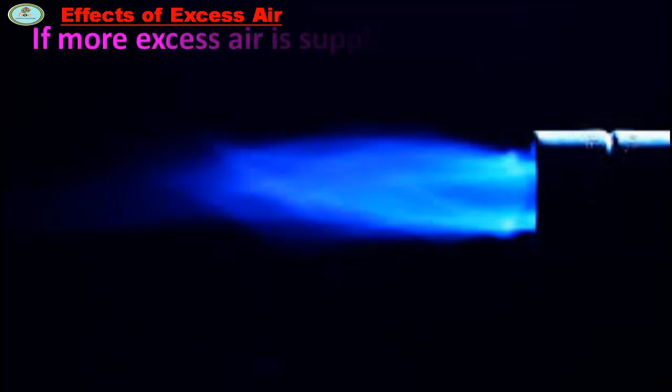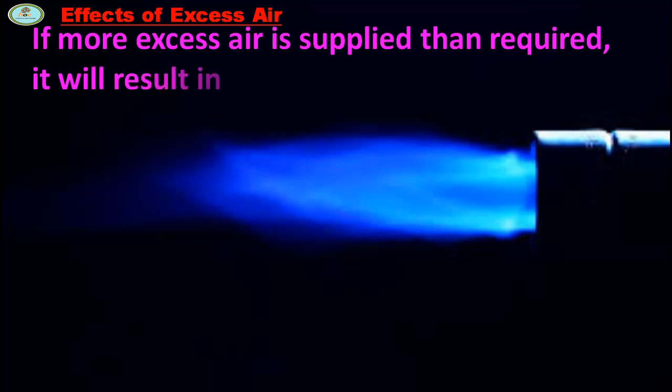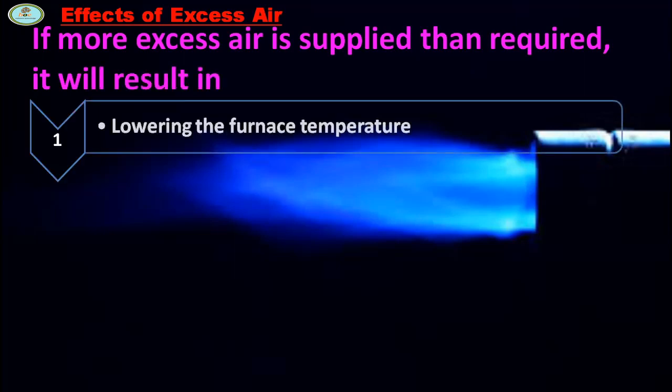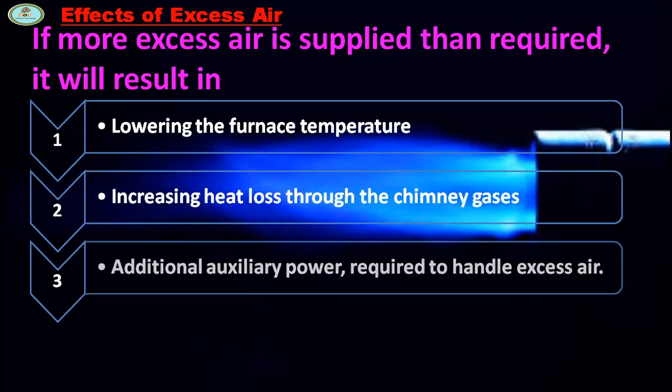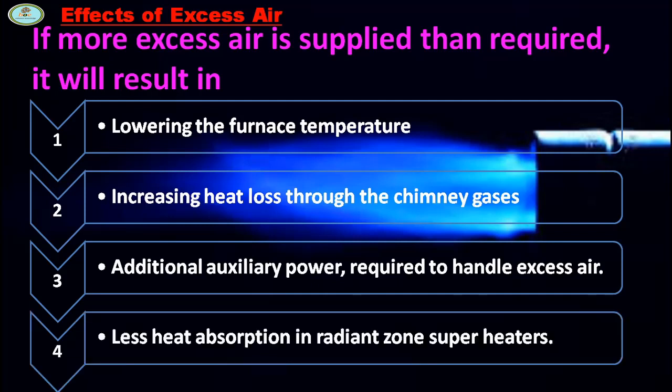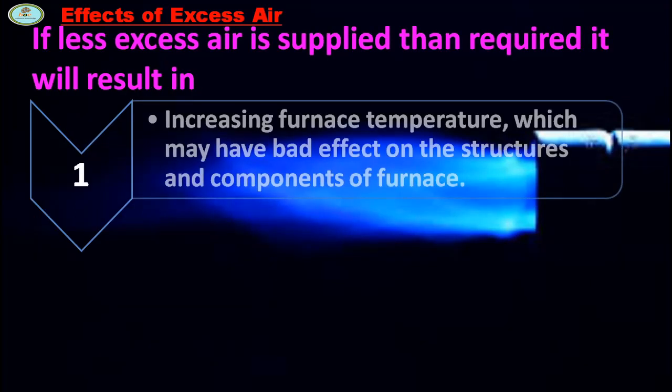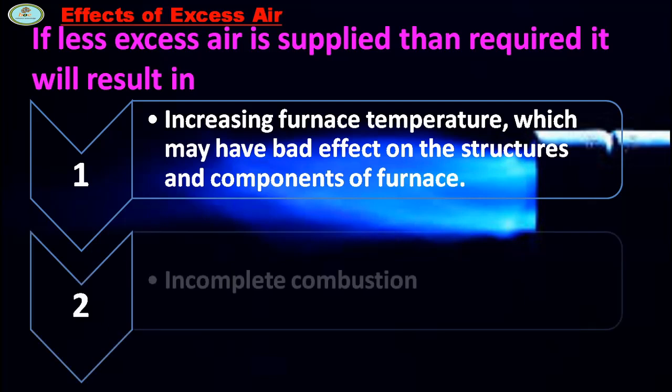Effect of excess air: If more excess air is supplied than required, it will result in lowering the furnace temperature, increasing heat loss through the chimney gas, additional auxiliary power required to handle excess air, less heat absorption in radiant zone, superheaters increasing furnace temperature, which have bad effect on the structure and components of furnace, incomplete combustion.